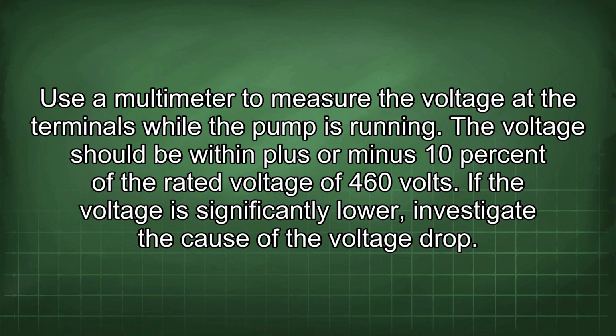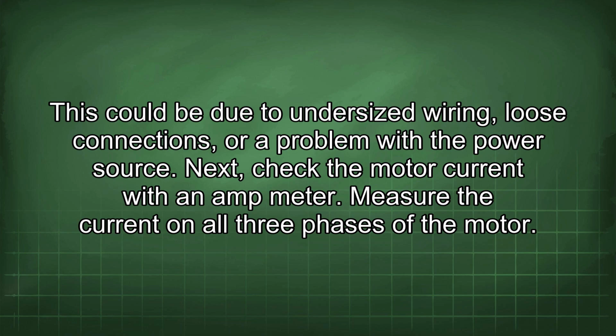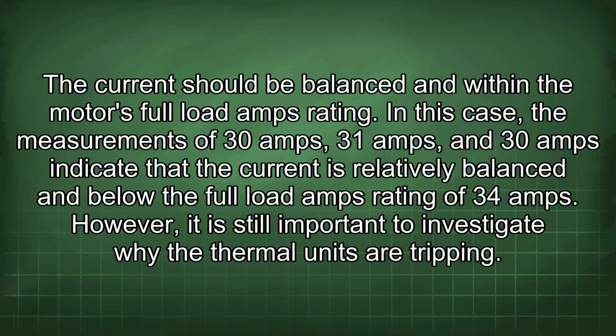If the voltage is significantly lower, investigate the cause of the voltage drop. This could be due to undersized wiring, loose connections, or a problem with the power source. Next, check the motor current with an ammeter. Measure the current on all 3 phases of the motor. The current should be balanced and within the motor's full load amps rating.